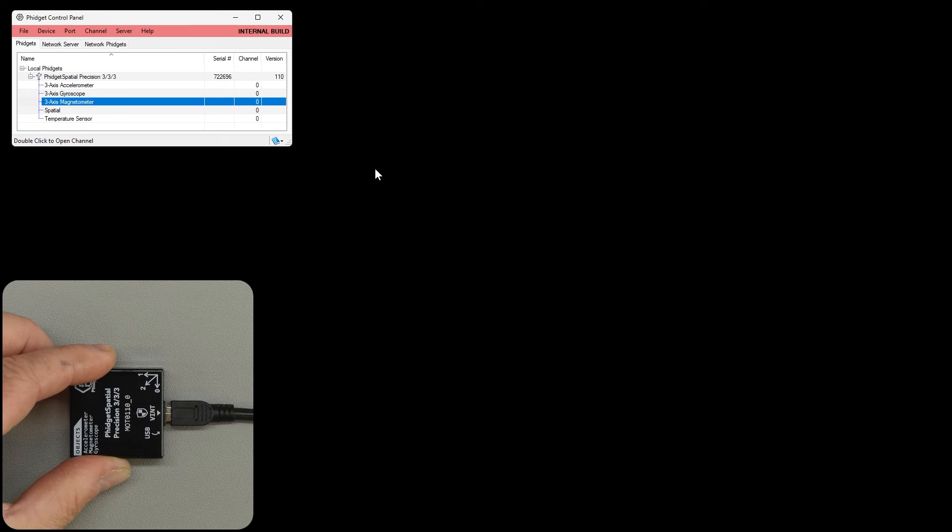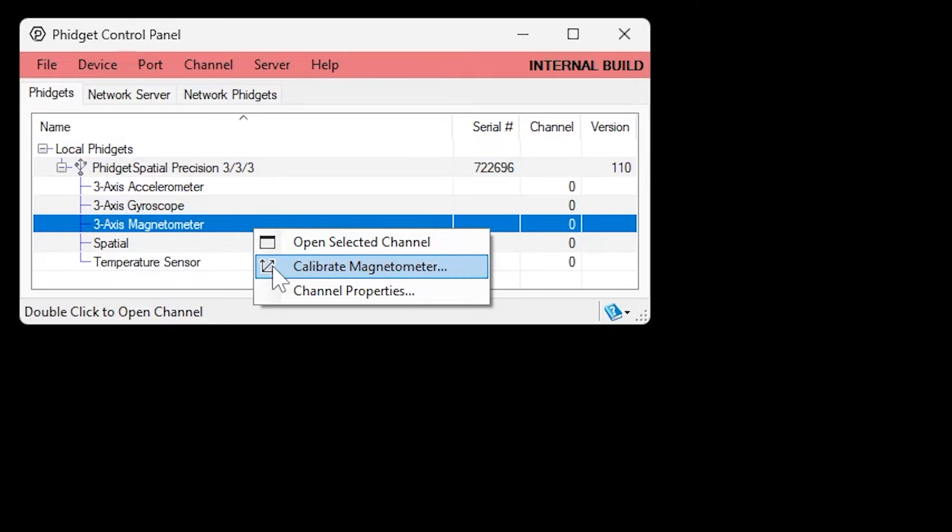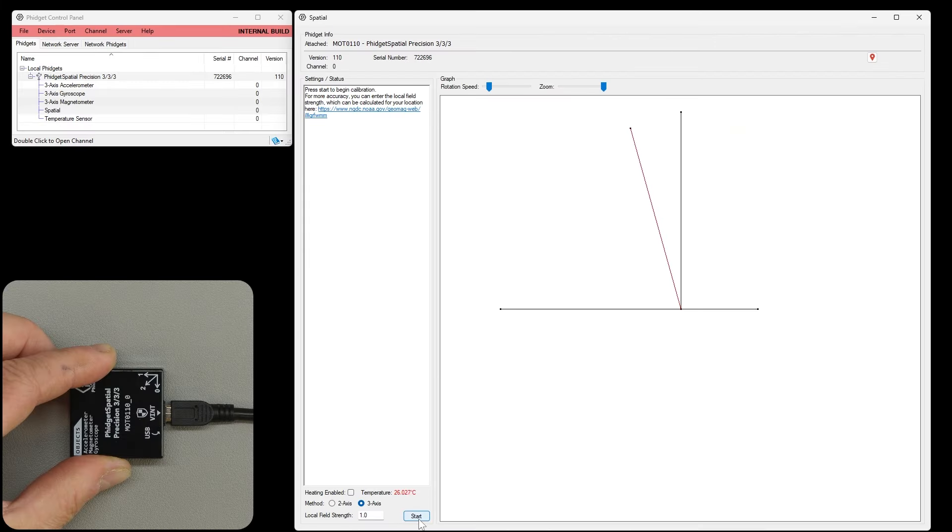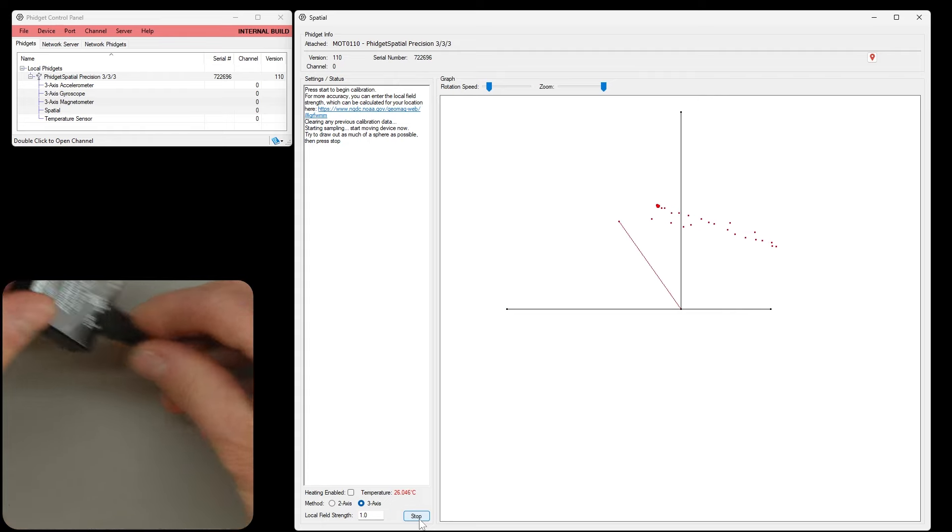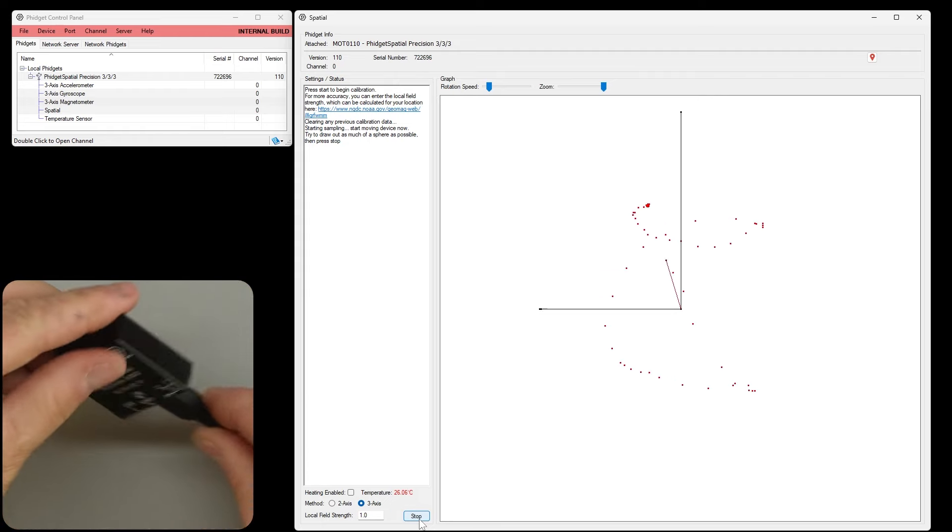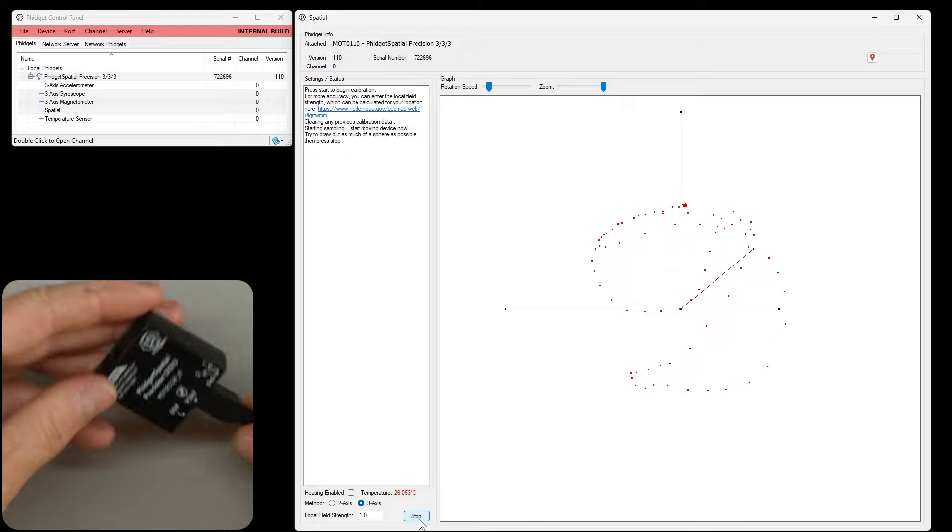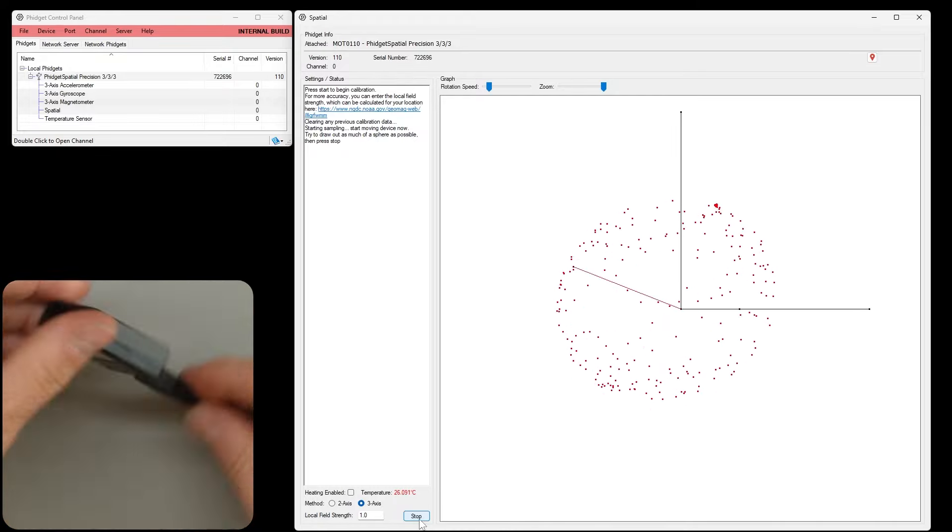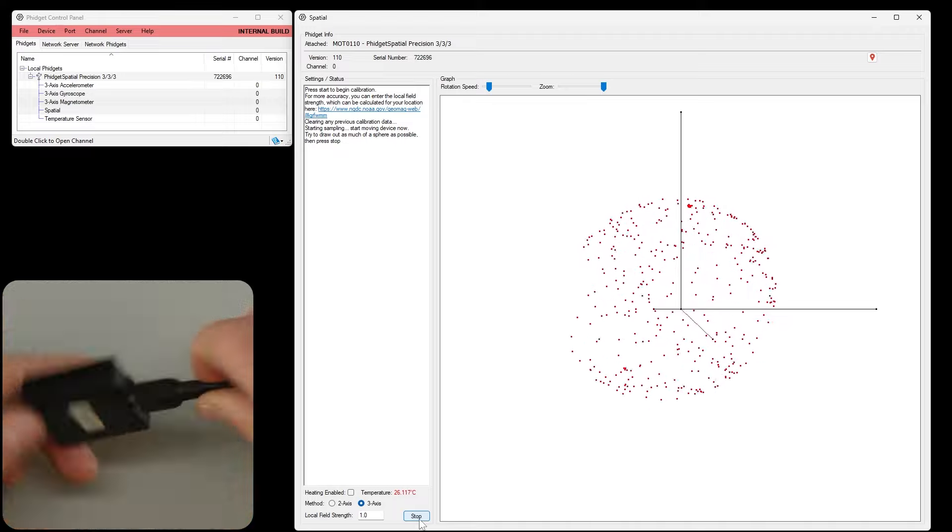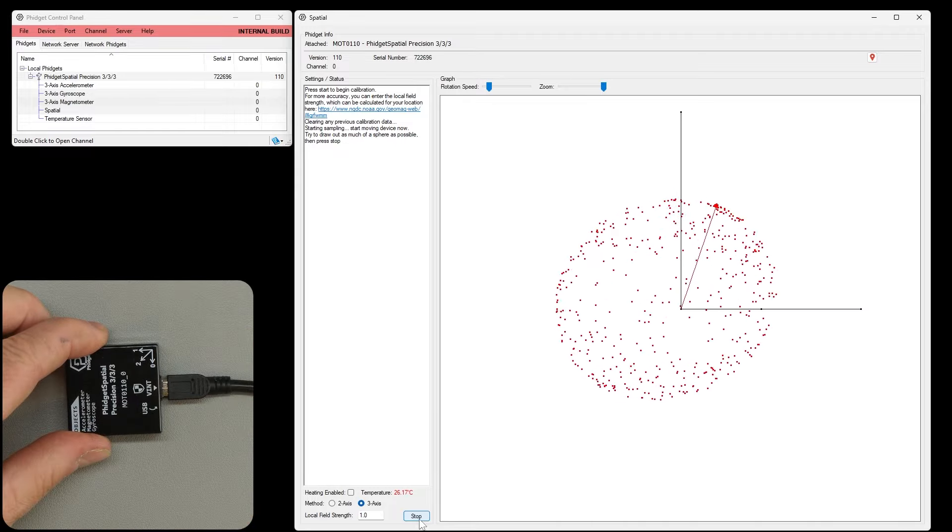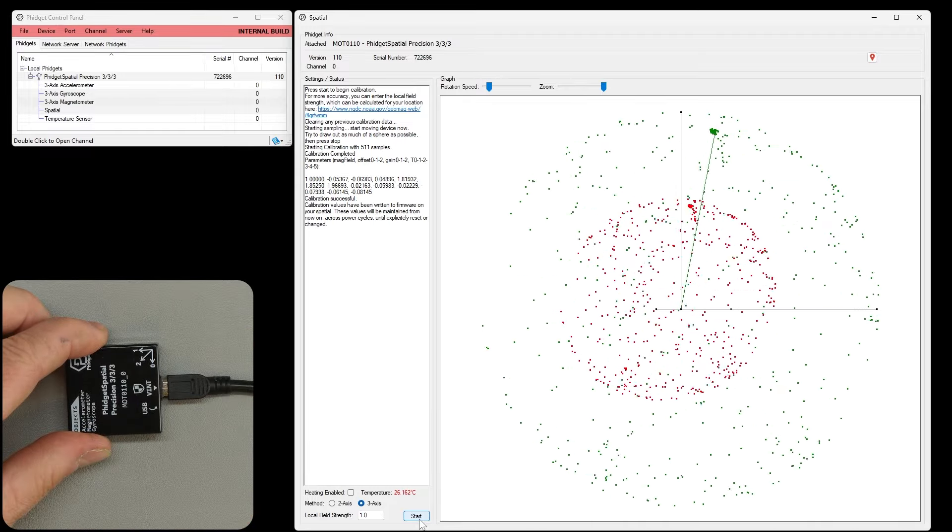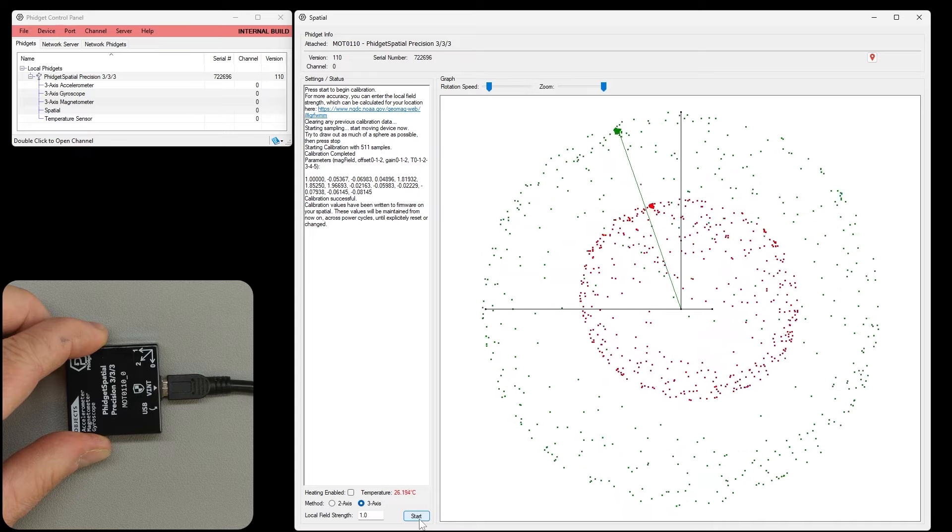Magnetometers are calibrated after they're installed in their application. We have a calibration utility that will help correct for any local magnetic interference. Since I'm doing a three-dimensional calibration here, I'm swinging the sensor to sweep out all range of possible motions. And calibration is complete.